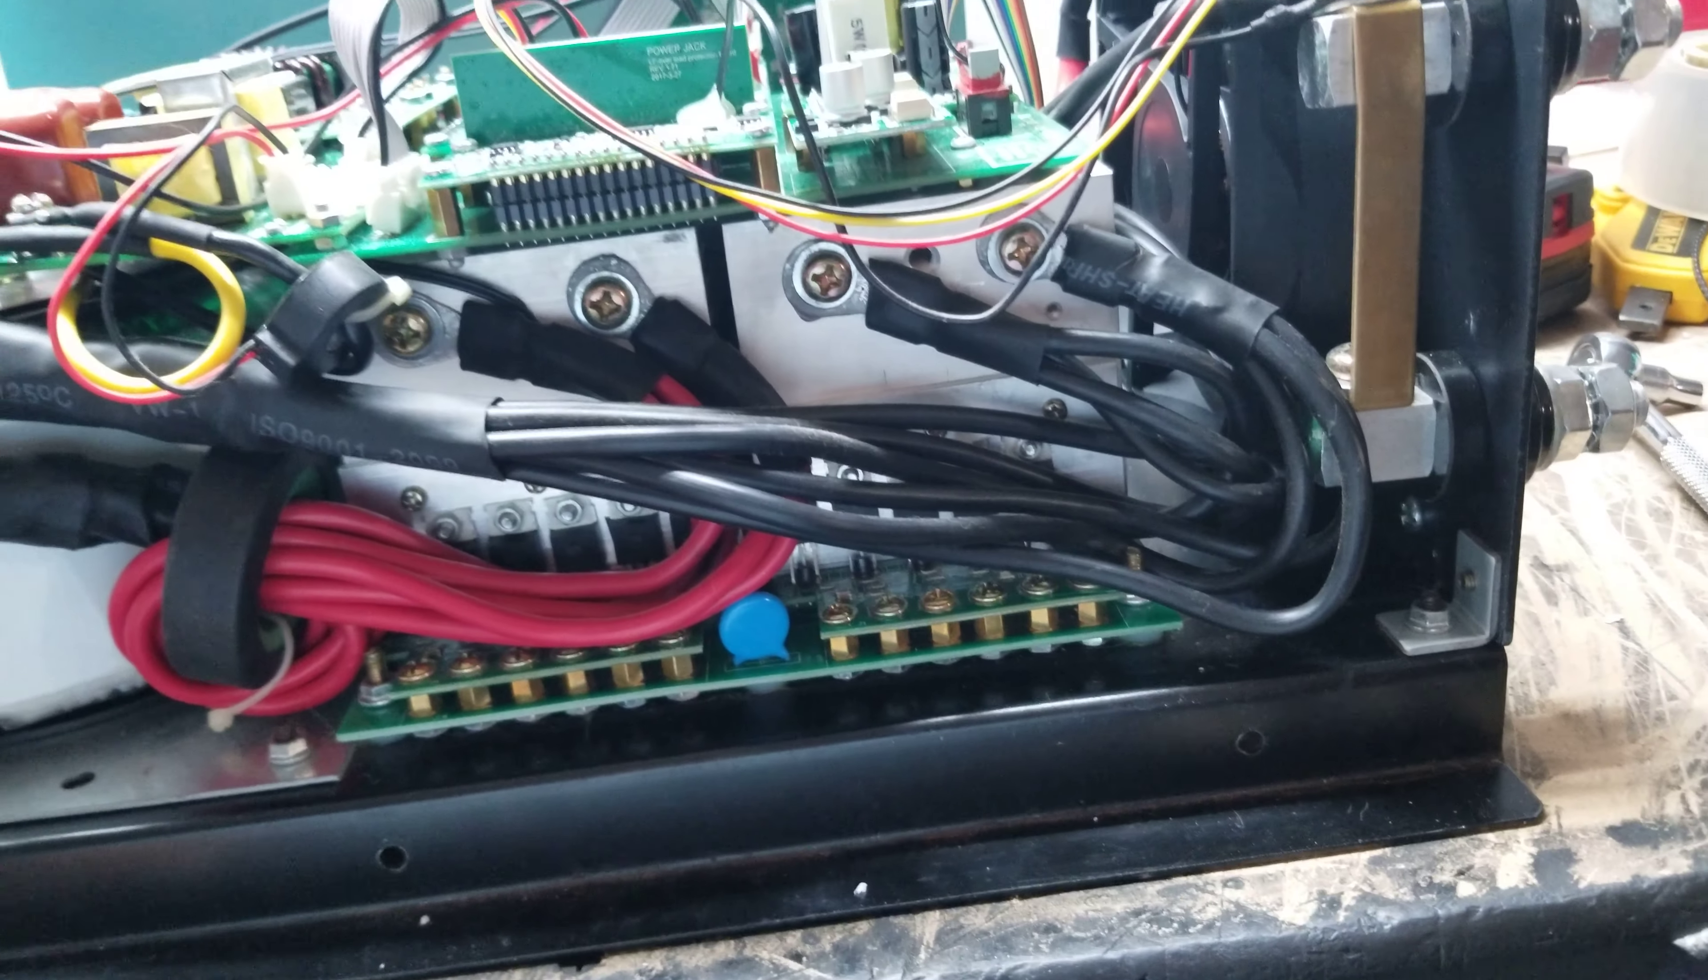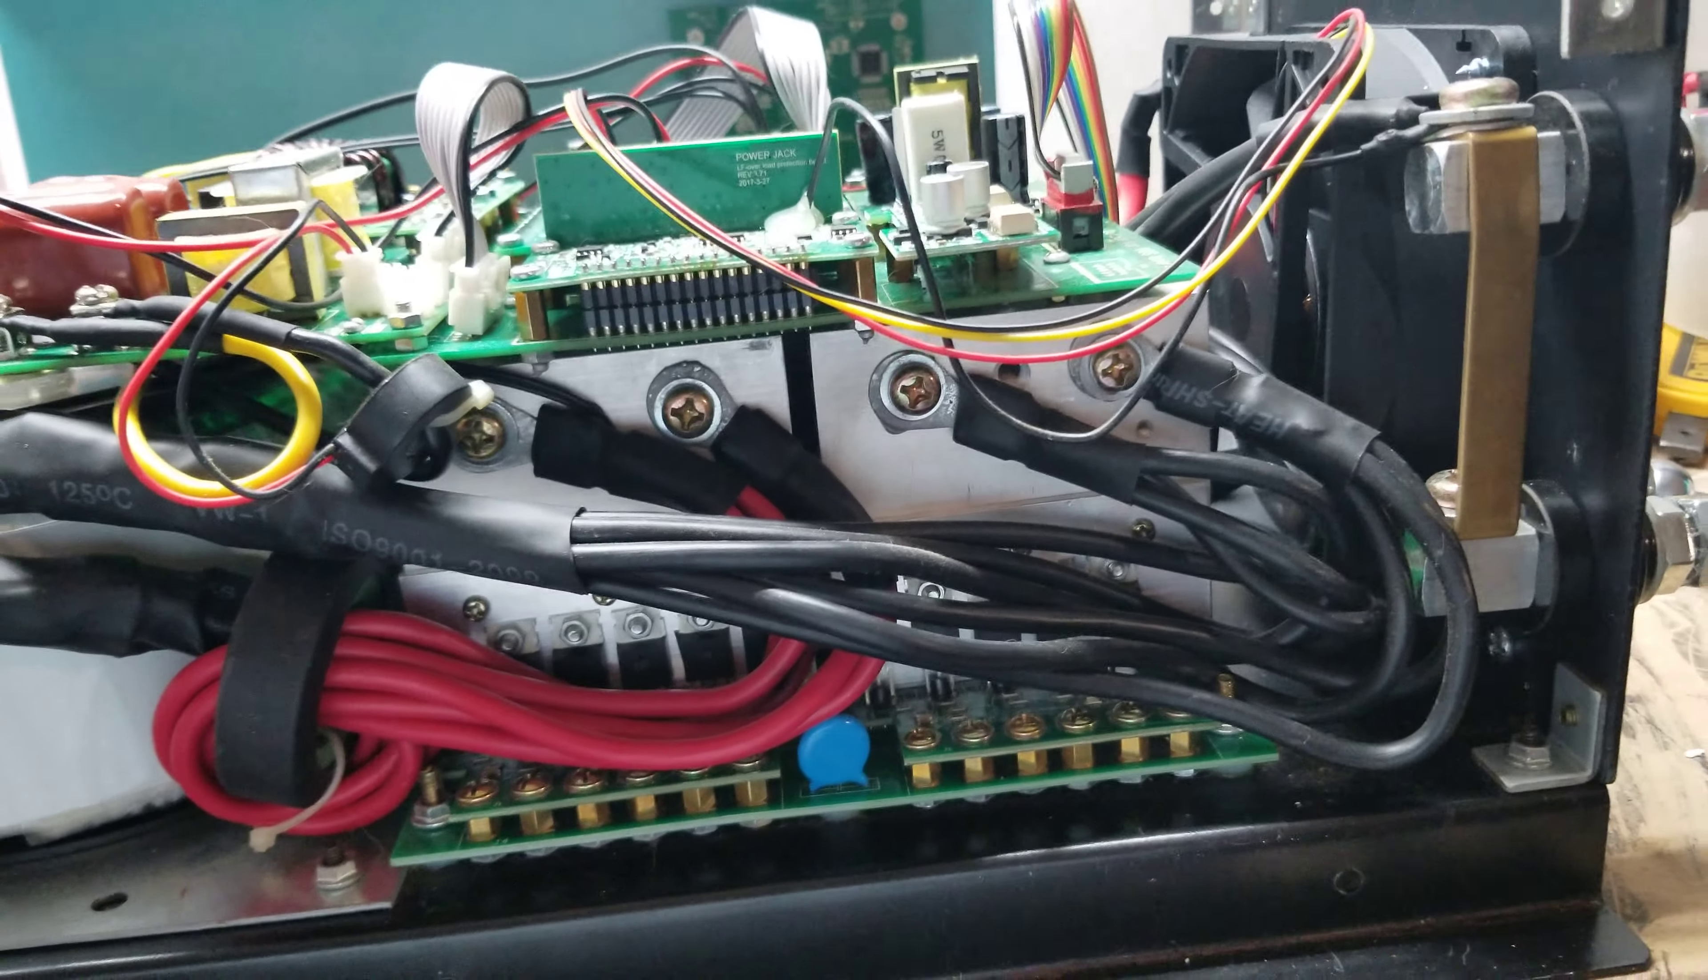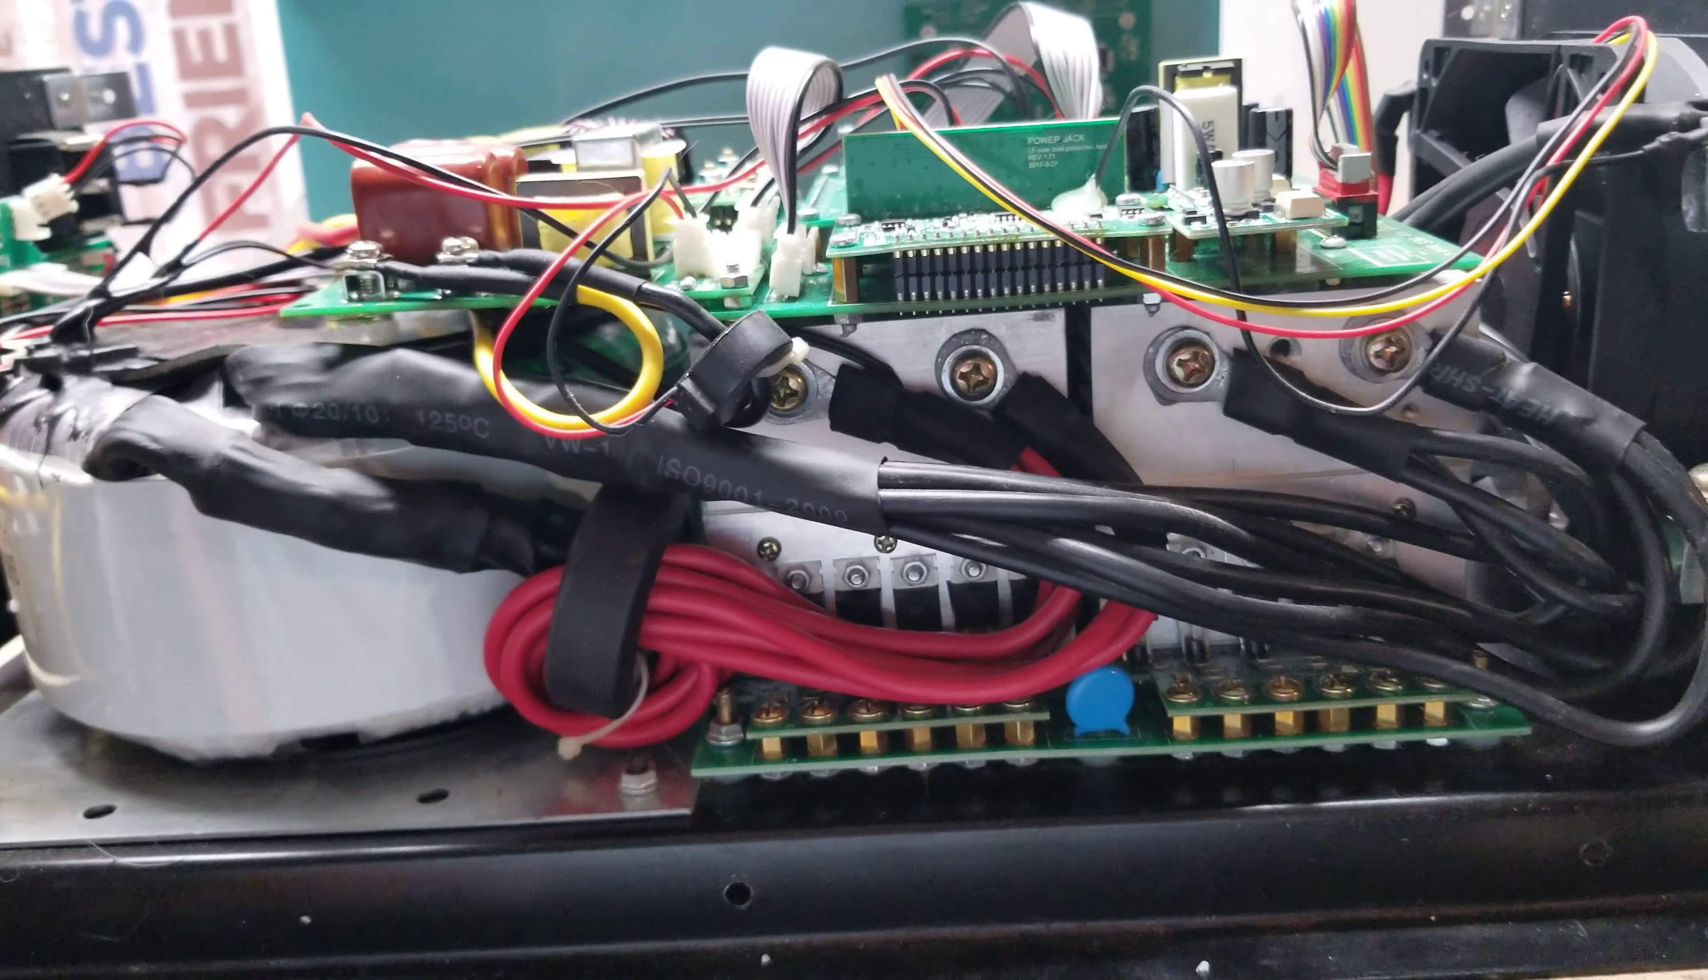So if you have one board that fails, it's a good idea to replace all four, or all eight if you happen to have a 15-kilowatt unit, as well as the low-frequency driver. Replace that. It's always a good idea to do that.